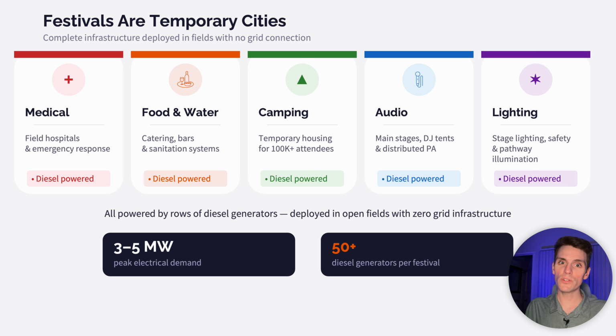These events are essentially temporary cities. They have medical facilities, food operations, camping for 100,000 people, massive sound systems, and stage lighting, all powered by rows of diesel generators deployed in fields with no grid connection. Peak demand reaches 3 to 5 megawatts, supplied by 50 or more generators per event.